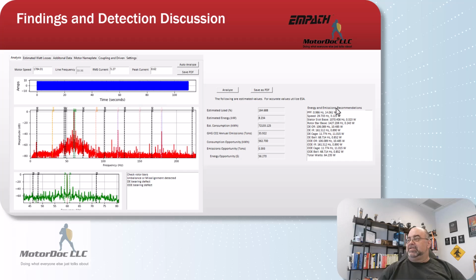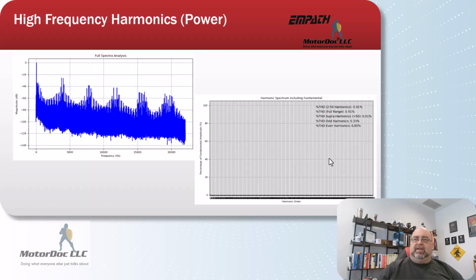But in any case, looking at the pole pass frequency, this is the energy lost associated with the rotor bar or the casting voids. Speed belt could be more significant, but in total we're only talking about 64 watts lost in that machine. When we start to, there's other things going on as well. And one of the reasons we developed the Empath was to get out to this higher frequency.